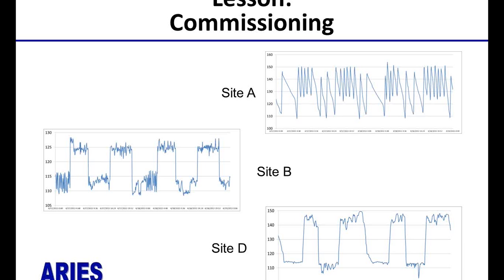Commissioning. This was another important take-home, something mentioned briefly in the previous presentation. So these three graphs show temperature modulation, typical 48-hour supply temperatures for the three buildings where we installed these controls. And what's happening in the first graph for Site A, you can see that the lower bound is indeed hitting that 110 and 125 degree set point that was programmed into the control, but for some reason the boiler is responding to a 20, 30 degree differential and raising the temperature well above that. And of course, the average temperature was skewed up and the savings were diminished.